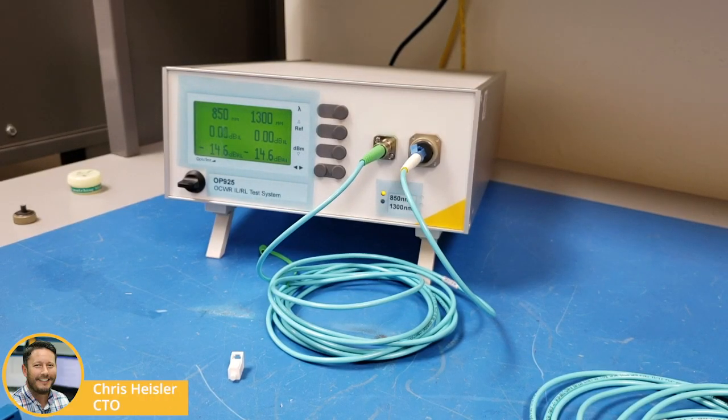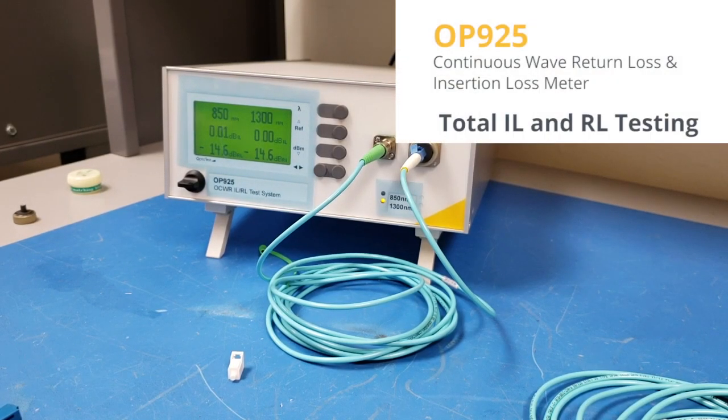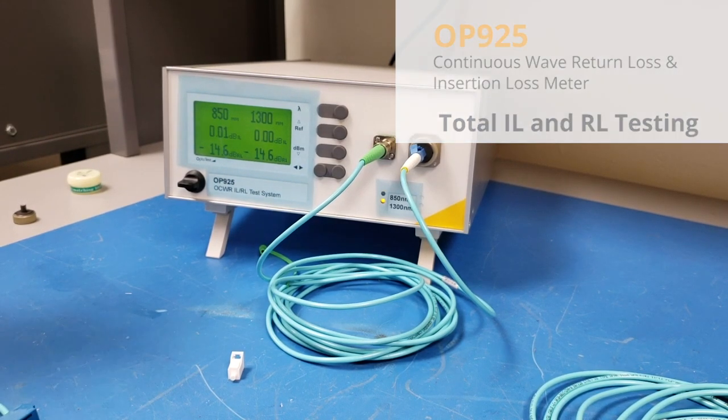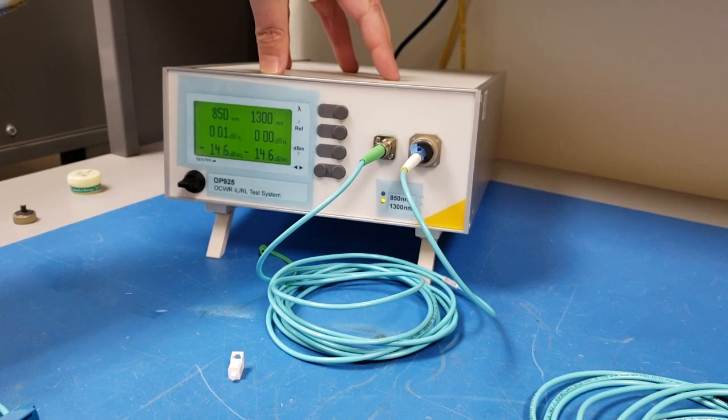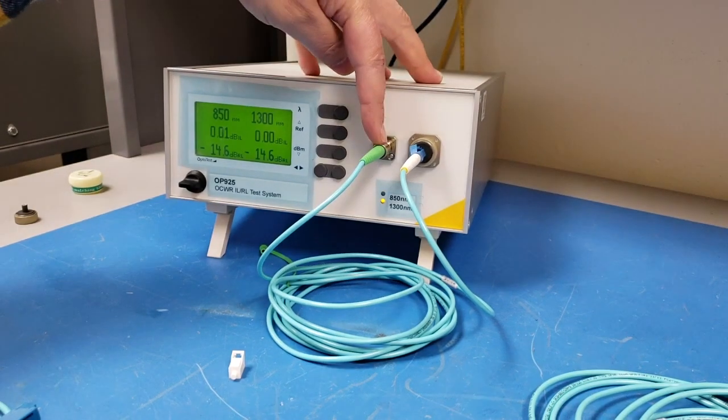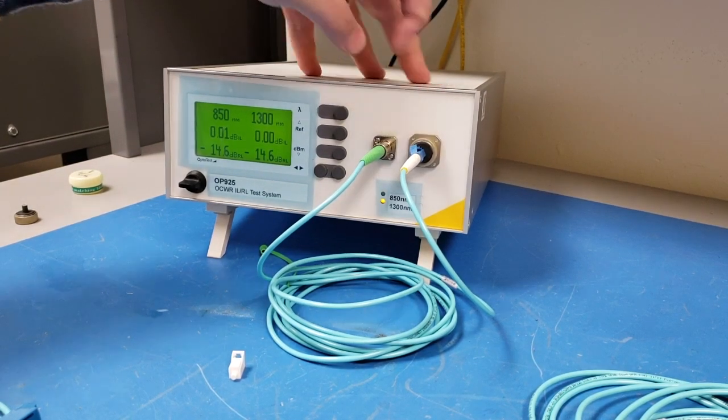Next we're going to look at testing the total IL and total RL of a DUT using the OP925. To do this, you're going to need to start with your instrument properly referenced with your launch cord connected from the source to the power meter.